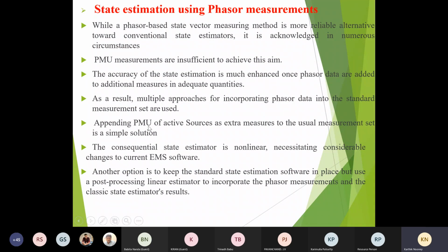But here, appending the PMU measurements to the usual measurement set is a simple solution, because a lot of software is developed in this way only. The consequential state estimate is non-linear, demanding considerable changes to the current EMS software. EMS means energy management systems. Another option is to keep the standard state estimation software in place, but use a post-processing linear estimator to incorporate the phasor measurements and the classic state estimator results.